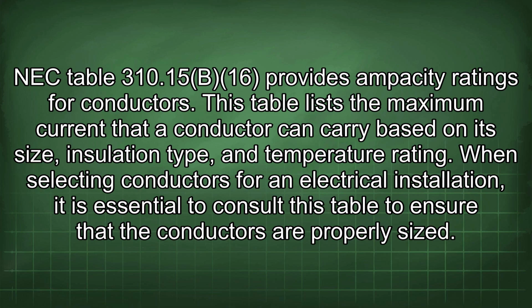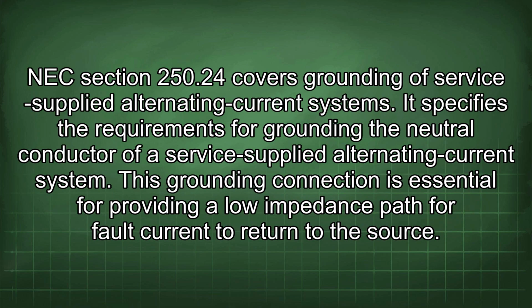NEC Table 310.15(B)(16) provides ampacity ratings for conductors. This table lists the maximum current that a conductor can carry based on its size, insulation type, and temperature rating. When selecting conductors for an electrical installation, it is essential to consult this table to ensure that the conductors are properly sized. NEC Section 250.24 covers grounding of service-supplied alternating current systems. It specifies the requirements for grounding the neutral conductor of a service-supplied alternating current system. This grounding connection is essential for providing a low-impedance path for fault current to return to the source.